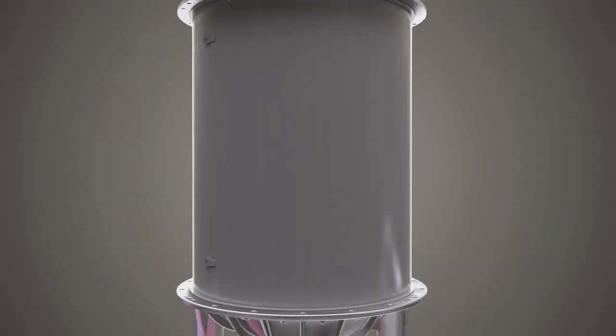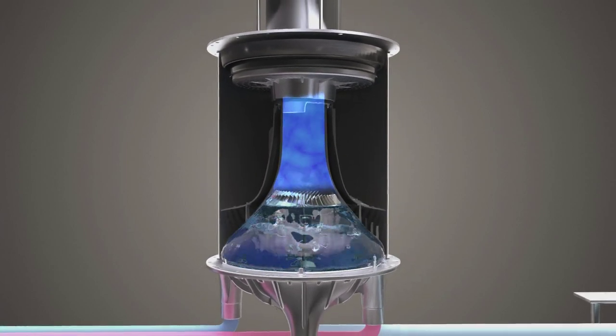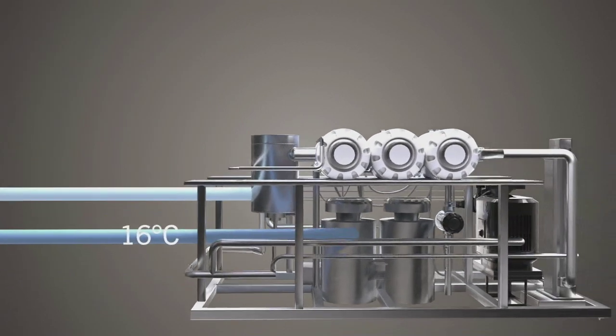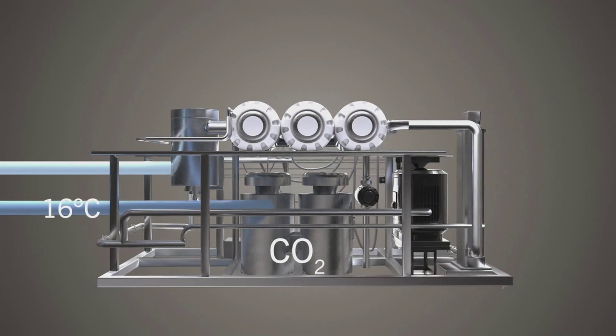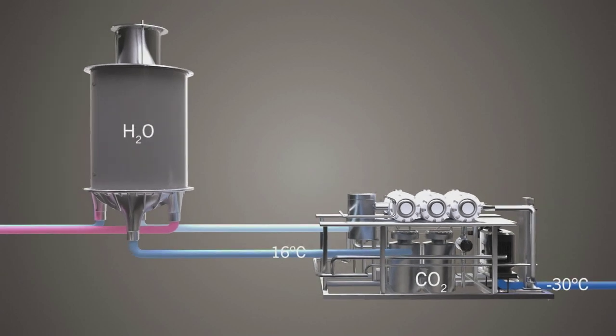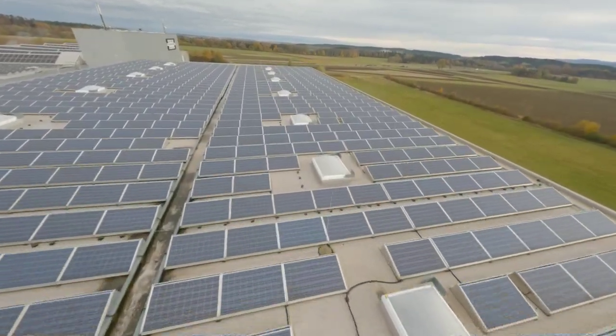The manufacturer is currently working with other companies in the field of cooling technology to realize a combination of CO2 refrigerators with water cooling systems in cascade form, supporting refrigeration technology with temperatures of minus 30 or minus 40 degrees Celsius. Here is how it would work: first, a cooling system using water as a coolant produces a water temperature of 16 degrees Celsius. An additional refrigerator using CO2 as a coolant then achieves temperatures well below the freezing point of water, expanding the range of possible applications. And if the CO2 refrigerant is captured from the atmosphere, this system becomes climate neutral as well.